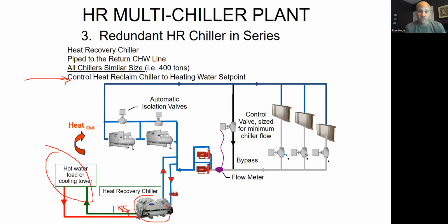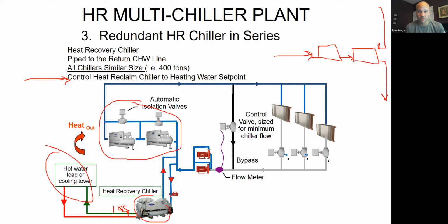In this case, though, I have these 2 chillers in series, and I'm probably going to put them in series counterflow. And that's a whole other class. But what series counterflow means, I don't know if I could draw it. I should have put a slide on here. Series counterflow means I've got my chilled water coming into one chiller, going into the next chiller, going out to the building, right? And then the condenser water comes in, and it's also running through those same 2 chillers in series, but it's counterflow to the other flow. So the chilled water is going this way, and the condenser water is going that way. That means the coolest condenser water gets to do work on the coolest chilled water.